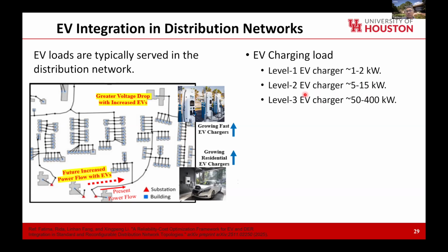For level three EV chargers, that would be the super charger, mainly for commercial EV charging stations. They are actually a large load. Even for level one and level two EV chargers, they are large loads compared to average home electricity consumption, which is just 1 to 2 kilowatts. I think nationwide the average is 1.3 kilowatts. So if you got a level one EV charger, you actually double your home electricity power. If you got a level two EV charger, you basically increase your home peak by a factor of 10.